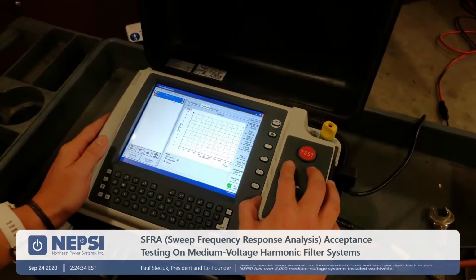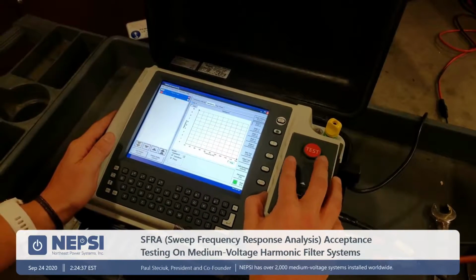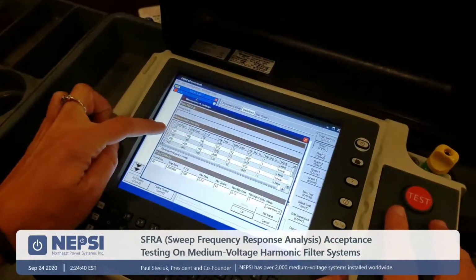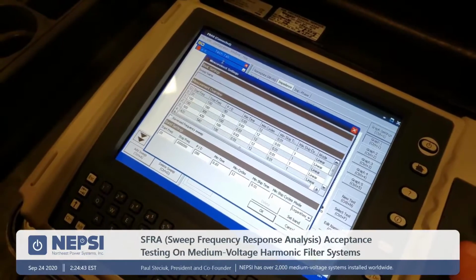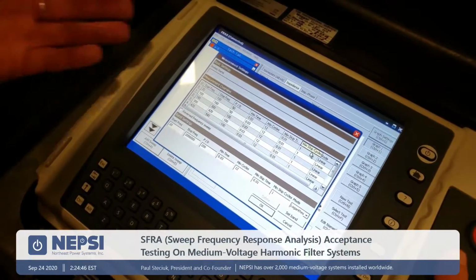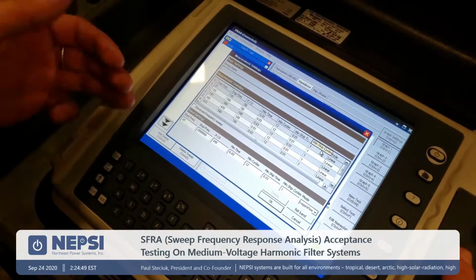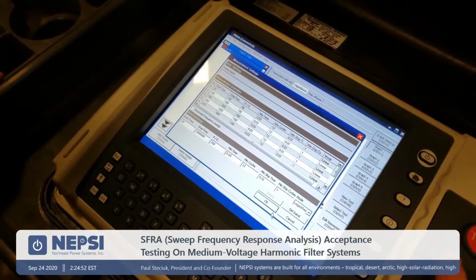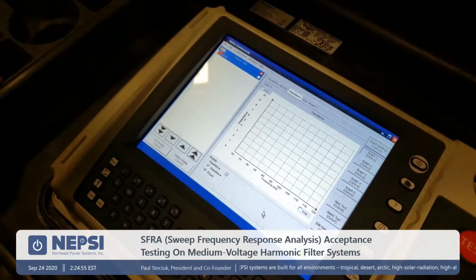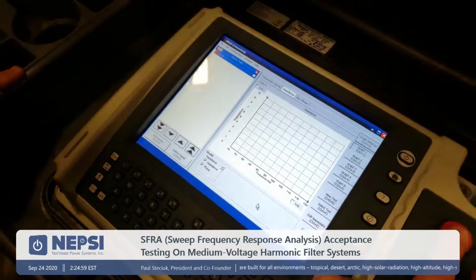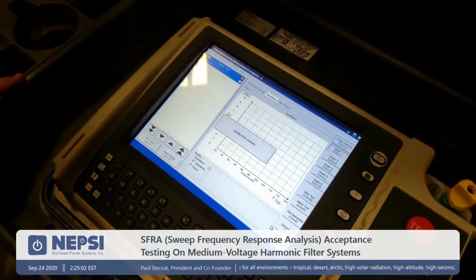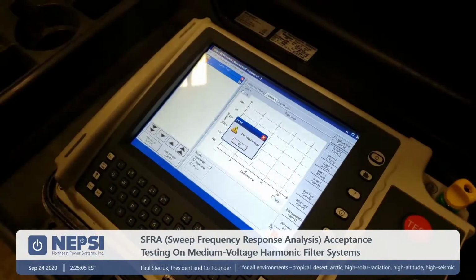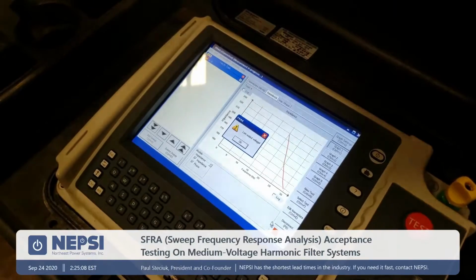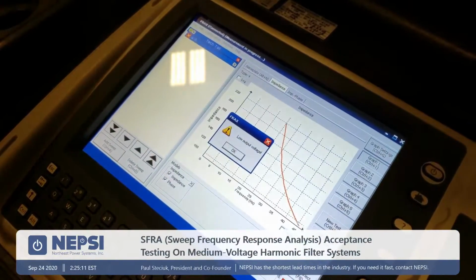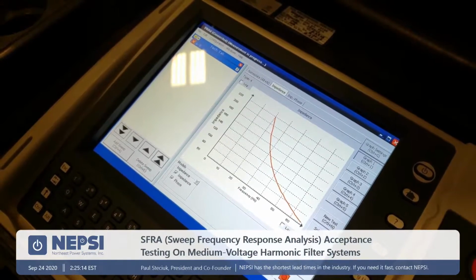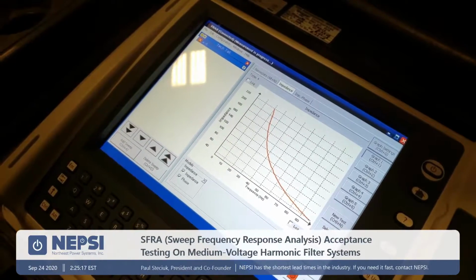And then for AB, I have my measurement settings. They're set as default right now, so they're all in there. So I'm starting at 20 hertz, so I'm going to sweep this entire unit from 20 hertz, and I go down to almost the 50th harmonic, and we set multiple bands to speed up the process of the scan. And after that, you can just hit test because we're connected to phase A and phase B. So what it's doing now is injecting volts and current into the system and it's measuring impedance as it goes on. Is that true, Jess? Correct. With a phase angle. With phase angle. Yeah, which I can show you the impedance phase.